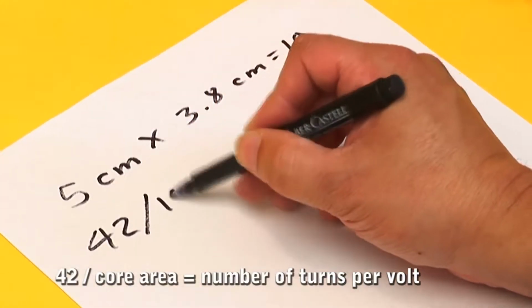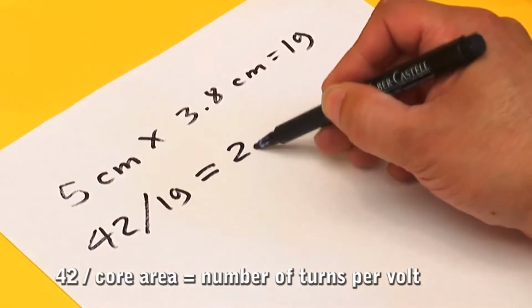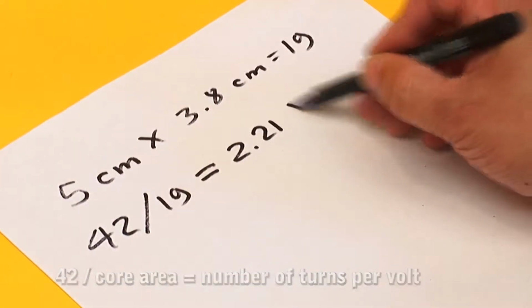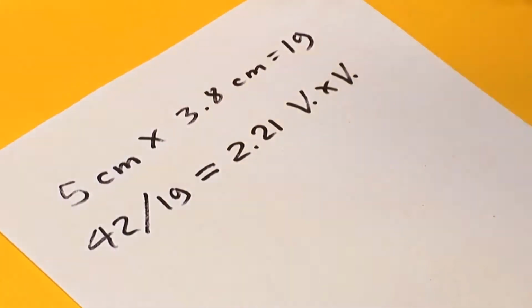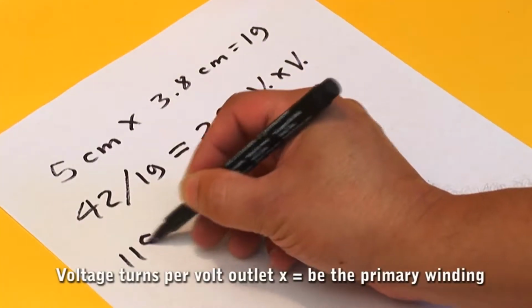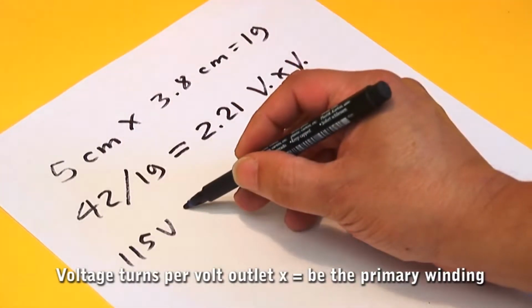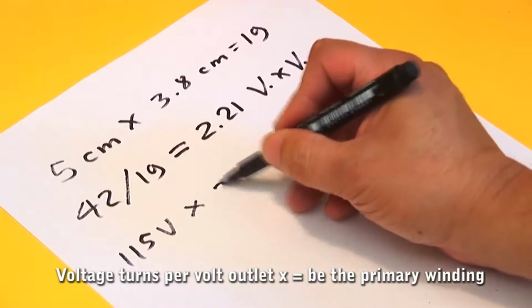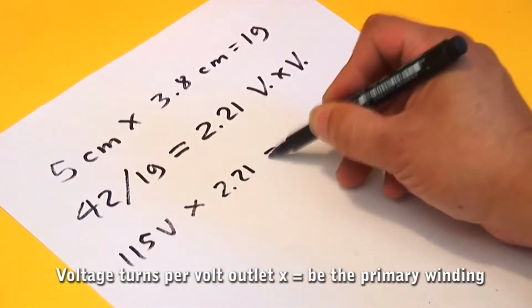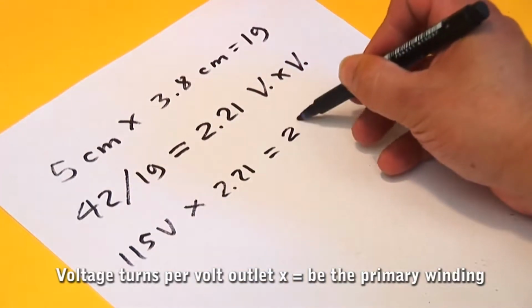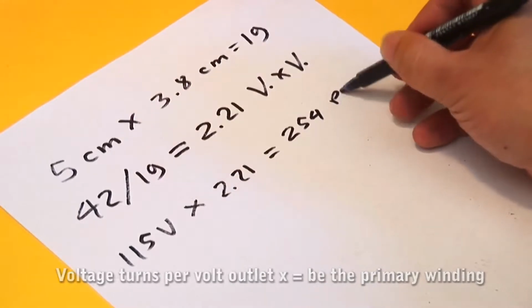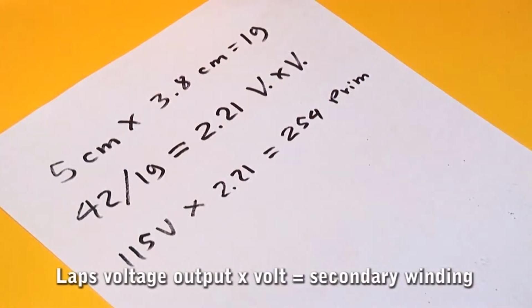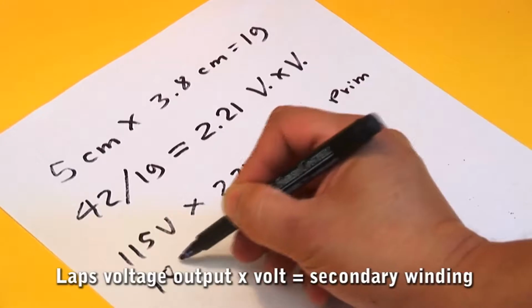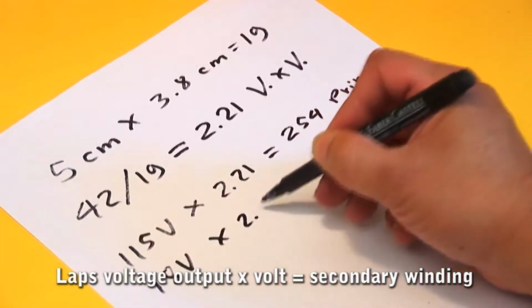We take the constant 42 and divide it by 19, giving 2.21 turns per volt. Since the public grid in our country supplies 115 volts, we multiply that by the number of turns per volt to get how many turns are needed in the primary winding. For the secondary winding, in this case 18 volts, we multiply by the number of turns per volt, and since we need 18-0-18 volts, the turns get doubled.